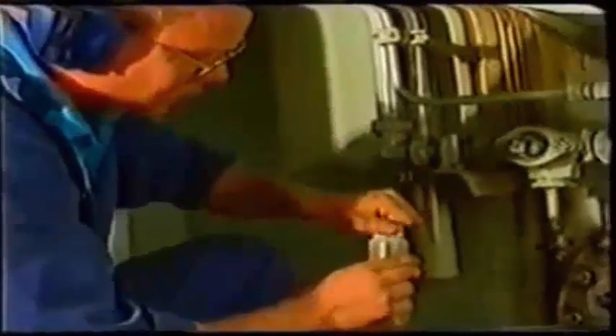The lubricant needs to be inspected and cleaned by filtering and centrifuge during its service life, according to manufacturers' recommendations. Finally, oil samples may be taken periodically from the lubricant in use and sent away for trend analysis to a laboratory on shore. There, the contaminant and metal particles in the oil are analyzed and quantified, and a picture built up of the state of health of the machine using that lubricant. Oil sample analysis is being dealt with in greater detail in Program 2.